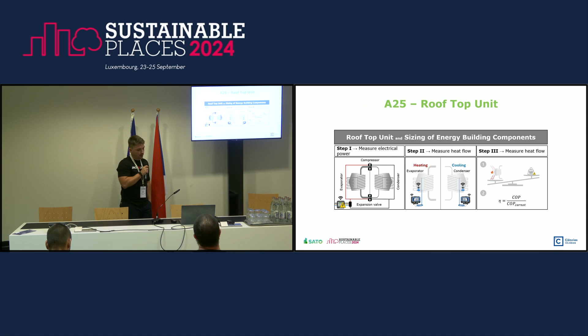Regarding the rooftop unit, this is a depiction of the assessment done in a heat pump, but basically the same, just using the air part of the system. We assess the heat transfer in the heat pump, and with the electricity use we can get the COP, then get the efficiency by taking the ratio with the COP of Carnot.